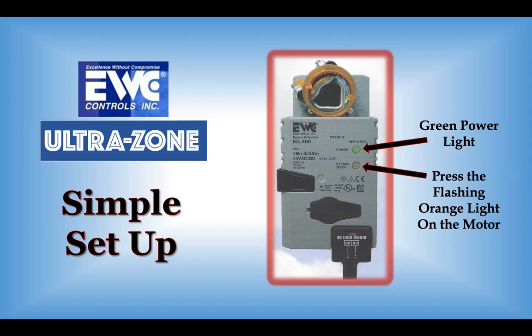What it's looking for is a 10% differential. Once it sees that, you'll come back to that motor 3 to 4 minutes later. That flashing light will be out. That means you're set to go. And this will now control the static in that system going forward. Even if you were to lose power, the static that it registered will stay in place.